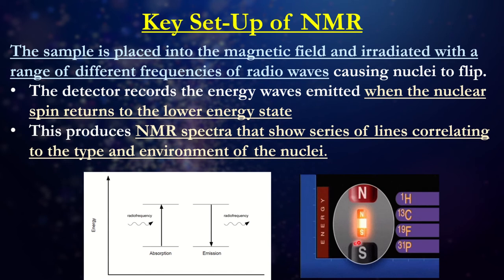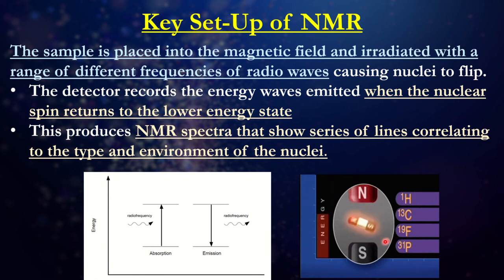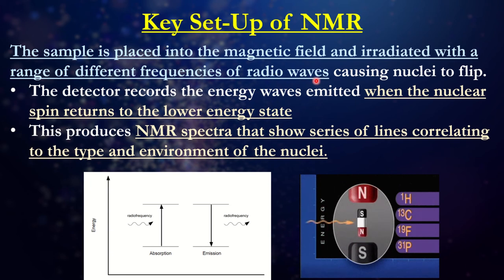Looking at the general structure of NMR: we have really powerful electromagnets, which use electricity to generate magnetic fields. We have a radio frequency generator that produces the radio waves, and then a detector that indicates the radio waves absorbed by our sample. When the sample is placed in the magnetic field, we irradiate it with different ranges of radio waves, causing nuclei to flip. The detector records the spin from the low or high energy state, and whatever peaks appear correlate with the type and environment of the nuclei.